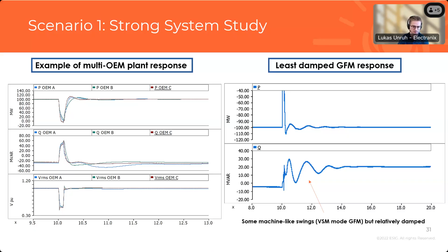On the right is probably the least damped grid forming response that we saw in this strong system study. Here you can see on the bottom plot some oscillations in Q that are damped in about 4 seconds, relatively quickly damped there.